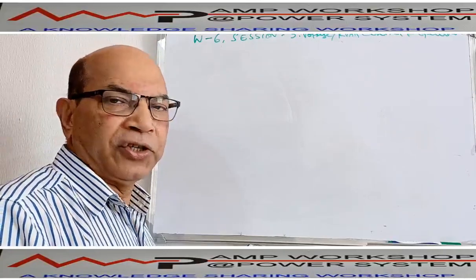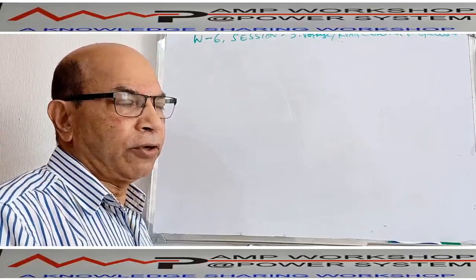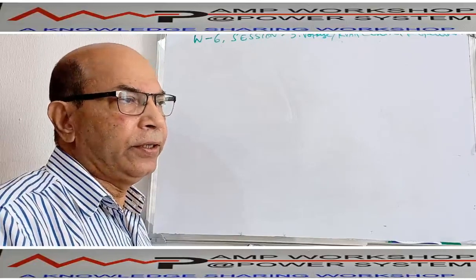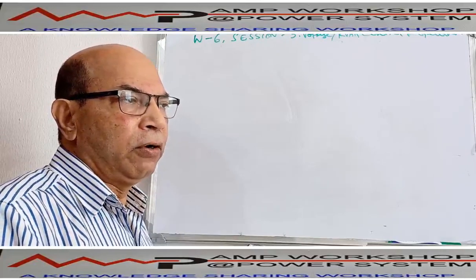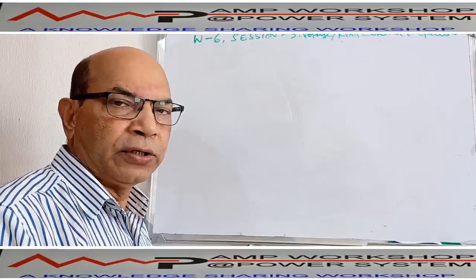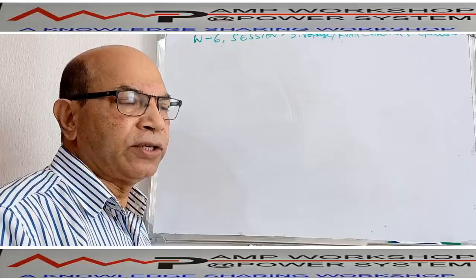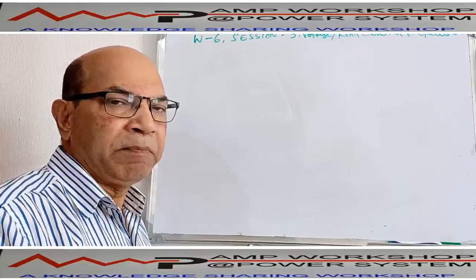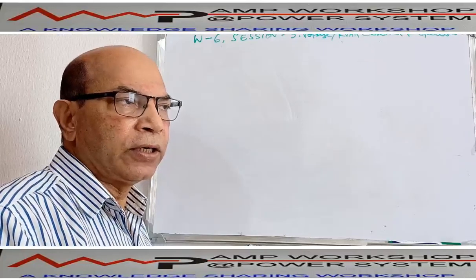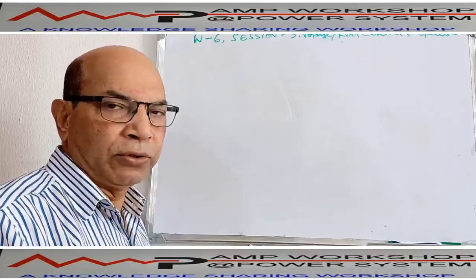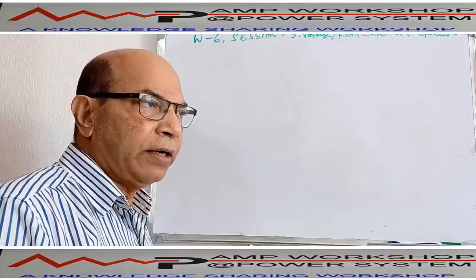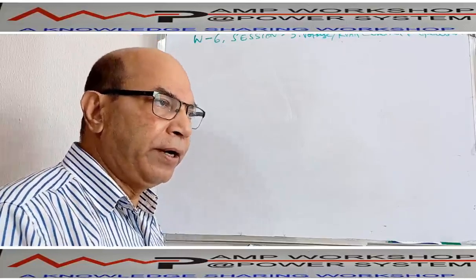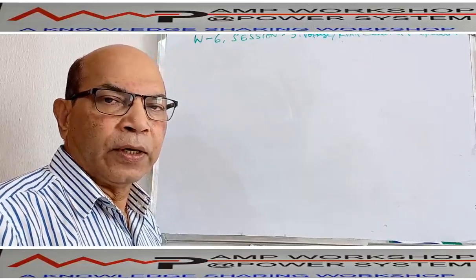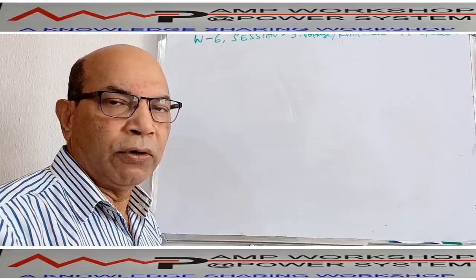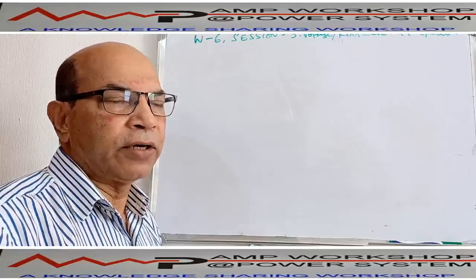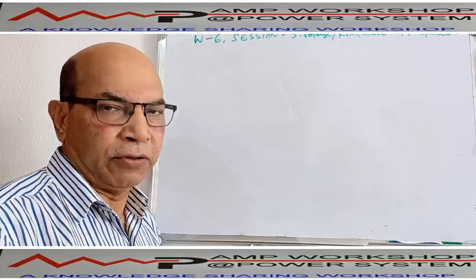We are discussing generator control under workshop 6, and in this workshop we have already completed 2 sessions where we have discussed synchronization and active power, that is kilowatt, and frequency or speed control. So the remaining items are pending, that is voltage control or VAR control, otherwise voltage control or reactive power control.